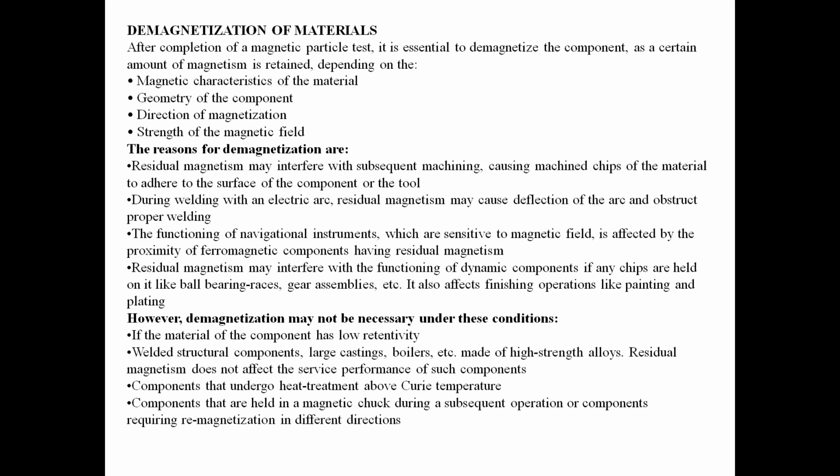Next, reasons. Why do we have to do this demagnetization? I already told, but point-wise I will explain. First one is residual magnetism: the magnetism retained after completion of the test may interfere with subsequent machining, causing machined chips of material to adhere to the surface. Already I told, while machining, the chips formed in the machining operation stick to the material because that material already has some magnetism.